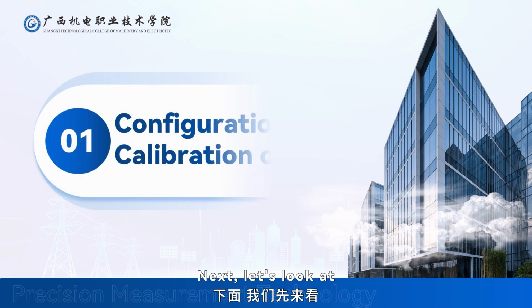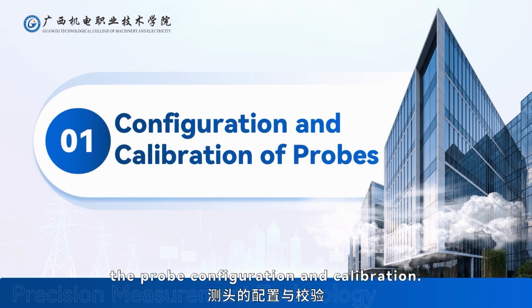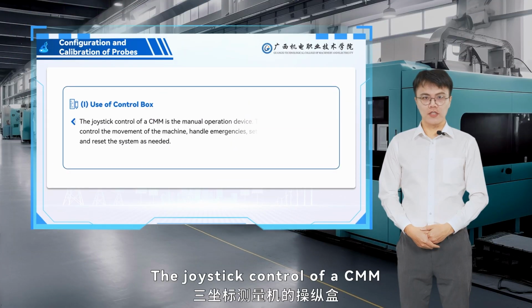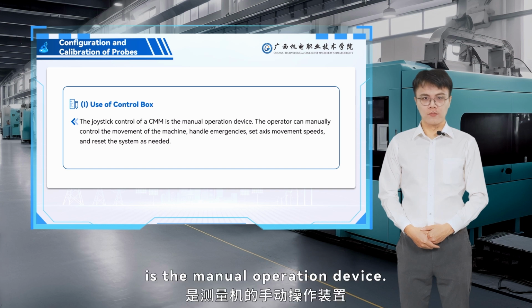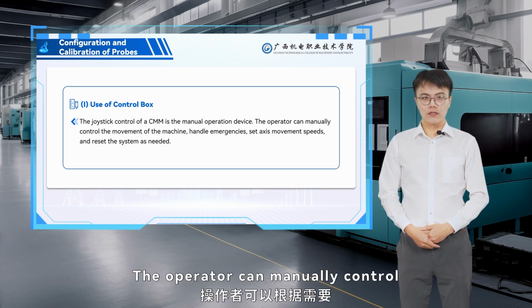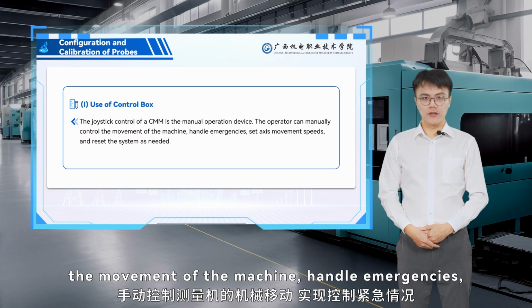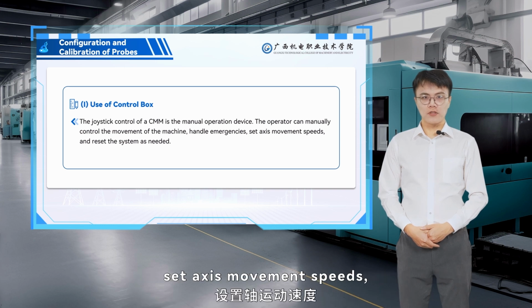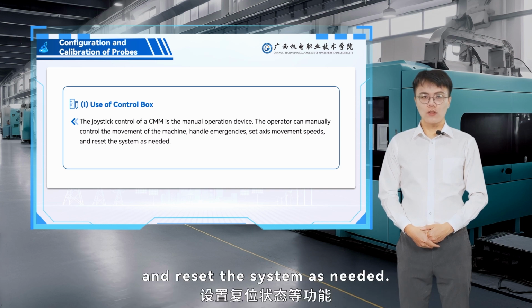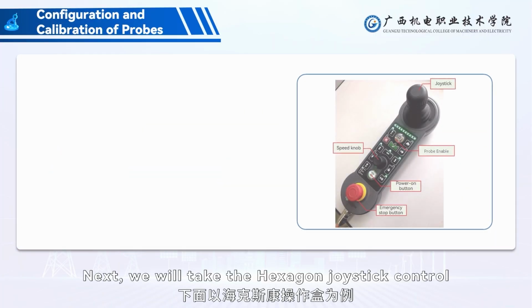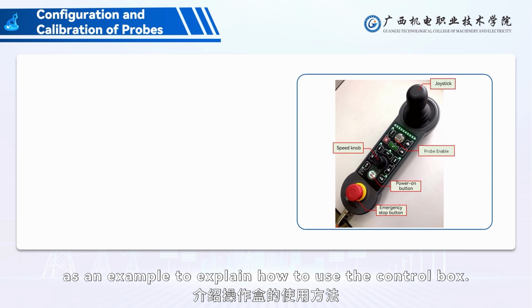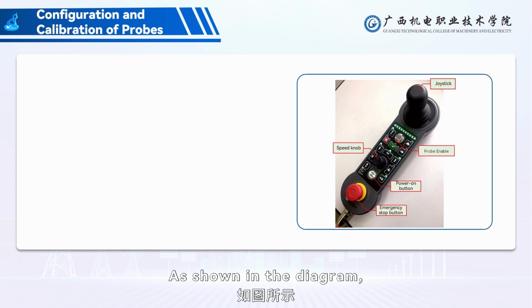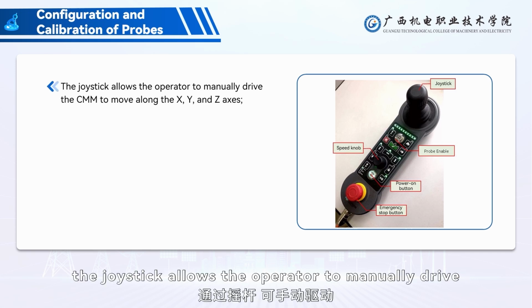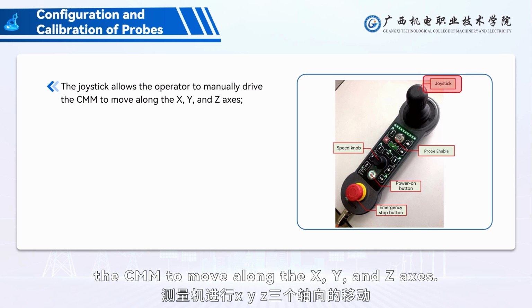Next, let's look at the probe configuration and calibration. The joystick control of a CMM is the manual operation device. The operator can manually control the movement of the machine, handle emergencies, set axis movement speeds, and reset the system as needed. Next, we will take the hexagon joystick control as an example to explain how to use the control box. As shown in the diagram, the joystick allows the operator to manually drive the CMM to move along the X, Y, and Z axis.